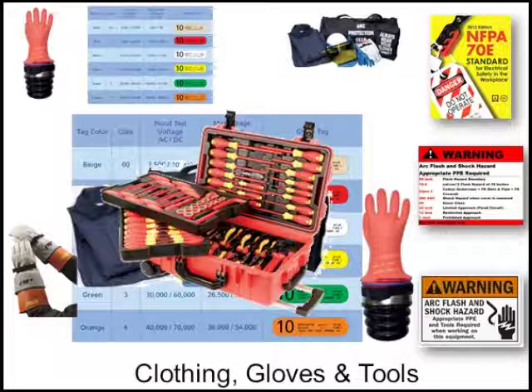Now, no matter what category of hazard we're working in, we're going to have to wear the proper clothing. Clothing boundaries are rated Category 0, 1, 2, 3, and 4. And Category 0 is the only level that doesn't require ARC-rated clothing. You still have to wear long-sleeve shirts, long pants, and hearing protection.